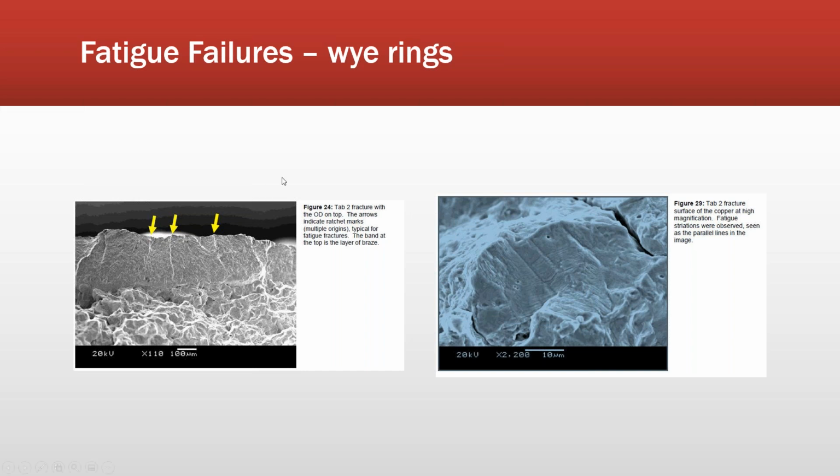Most studies, there's a ton of them published. Anybody ever goes to IEEE sites, you can look them up. I've got a pile sitting next to me about 18 inches high of 4-page studies and 2 books on the subject. Found it very interesting, and even more so when we got our hands on some windings that hadn't quite failed yet, and the generators were removed for other repairs. So one of the repair shops, Shermco in particular, had sent me this. They've been participating in the studies, as has Evans, as has H&N.